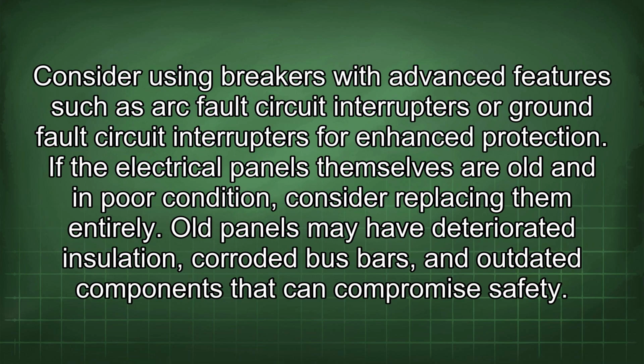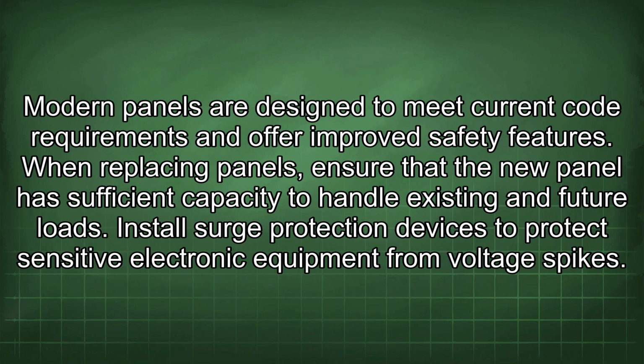Consider using breakers with advanced features such as arc fault circuit interrupters or ground fault circuit interrupters for enhanced protection. If the electrical panels themselves are old and in poor condition, consider replacing them entirely. Old panels may have deteriorated insulation, corroded bus bars, and outdated components that can compromise safety. Modern panels are designed to meet current code requirements and offer improved safety features. When replacing panels, ensure that the new panel has sufficient capacity to handle existing and future loads.